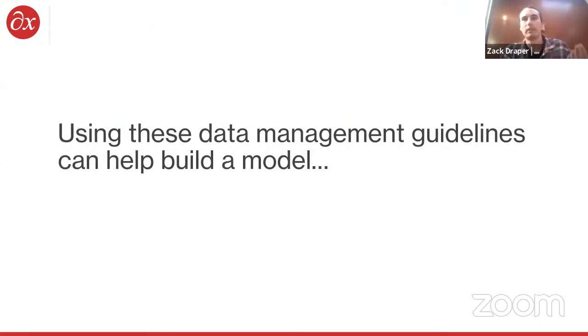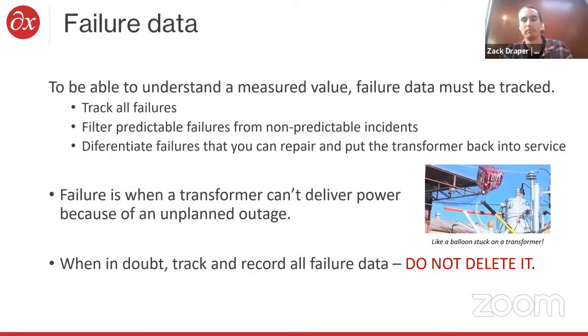So using data management, we can build these kinds of models. For dissolved gas analysis, when we were developing reliability-based DGA, we really wanted to correlate the gases with actual failure data. We didn't want to use the traditional assumption that the 90th percentile tells us what's risky or not risky. We wanted to look at what the failure data was telling us about the risk involved in that gassing. What that required is tracking all the failures, and it's not as common a practice in the industry as it should be. But by collecting all of those failures, we had something useful to go on.